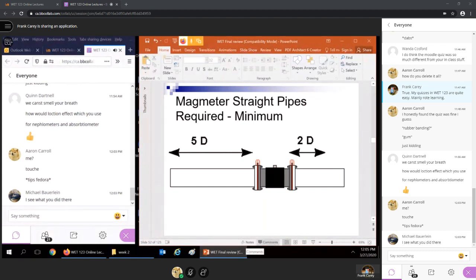Whereas orifice plates, Frank used to know the ISO standard for it, the industry standard. I believe it's like 30 diameters up and 10 down. It's pretty extreme, so it depends with every instrument. But in our course, I'll just ask about the magmeter, and just know that it's 5 diameters up and 2 down, with flow in this direction. I should almost have written that down.